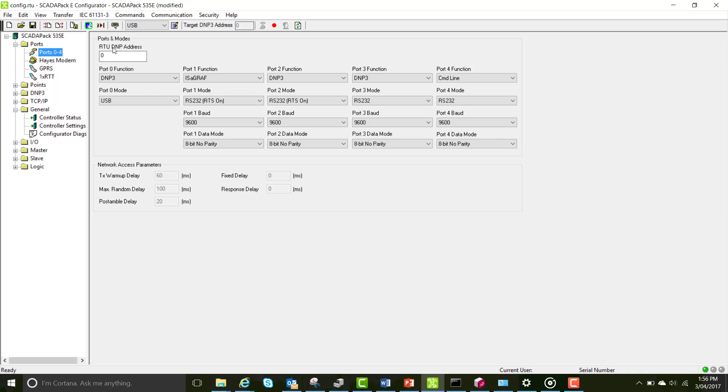After you factory reset, this will be zero. We need you to change this to a unique number. I'm going to use 12. This has to be unique because if we have two different RTUs at DNP address of 12 on the network and you try to communicate with slave device 12, the network will get confused and not know where to send that information.